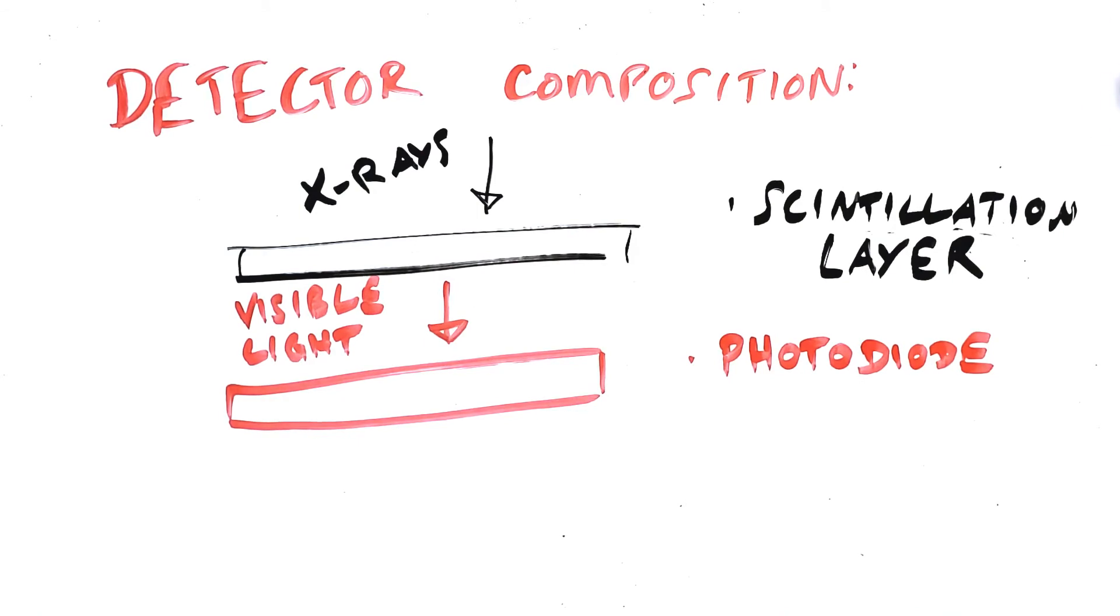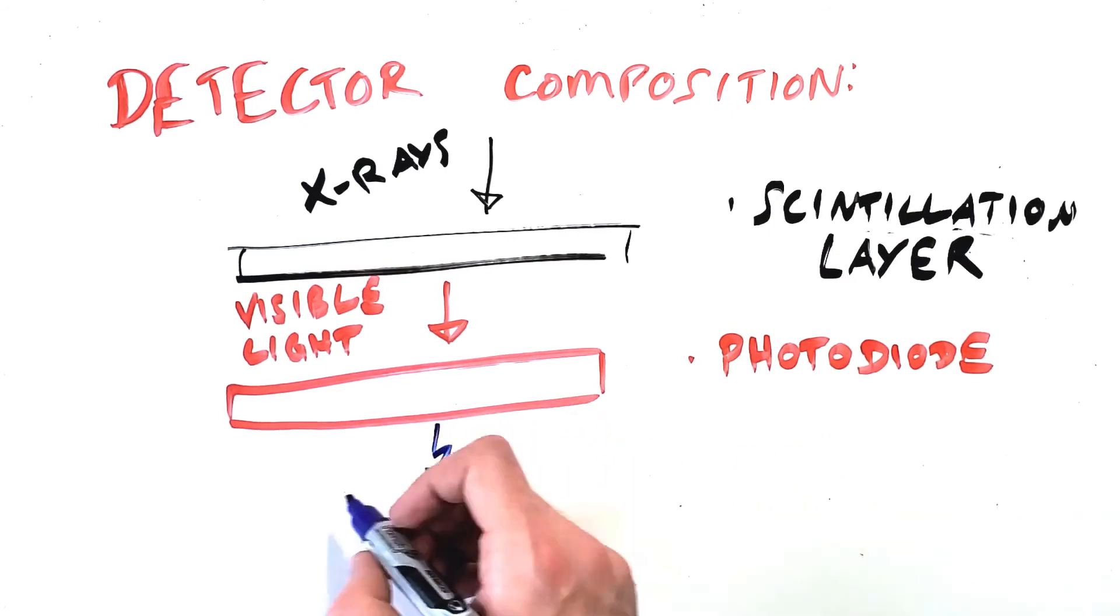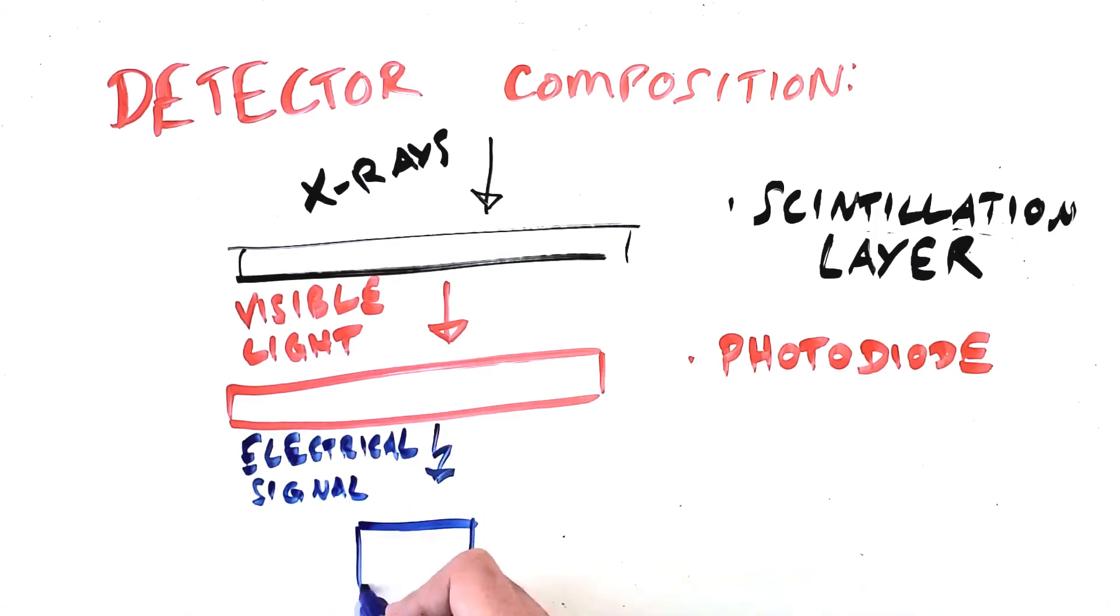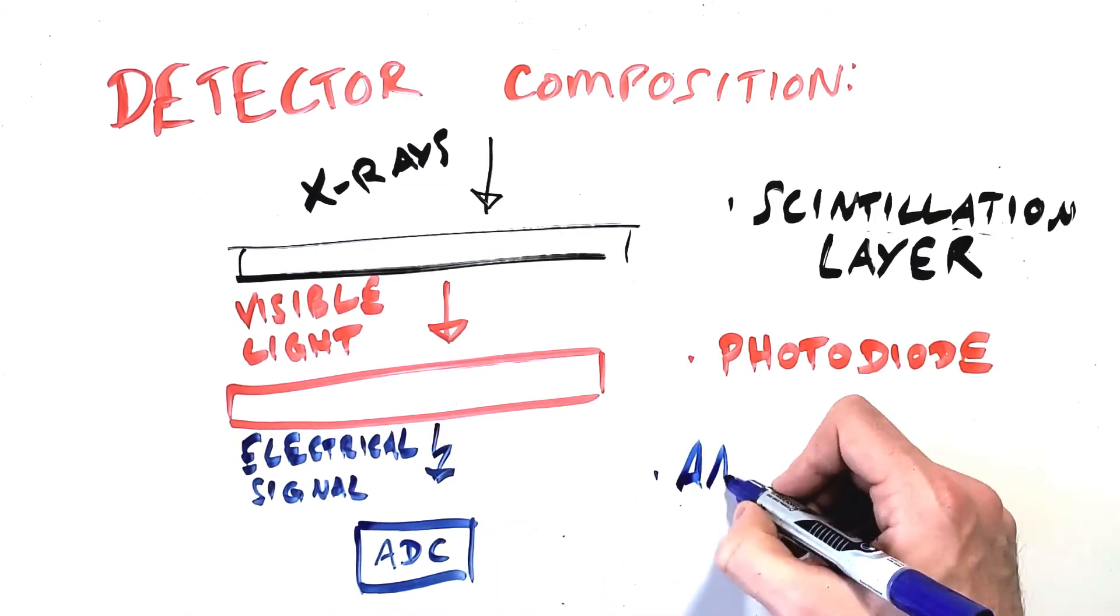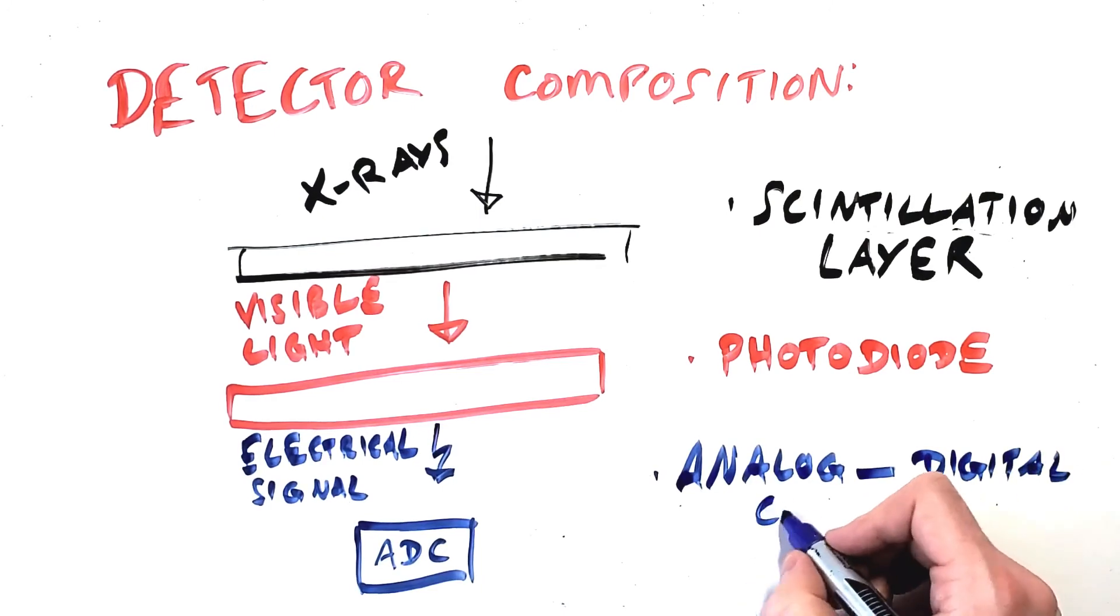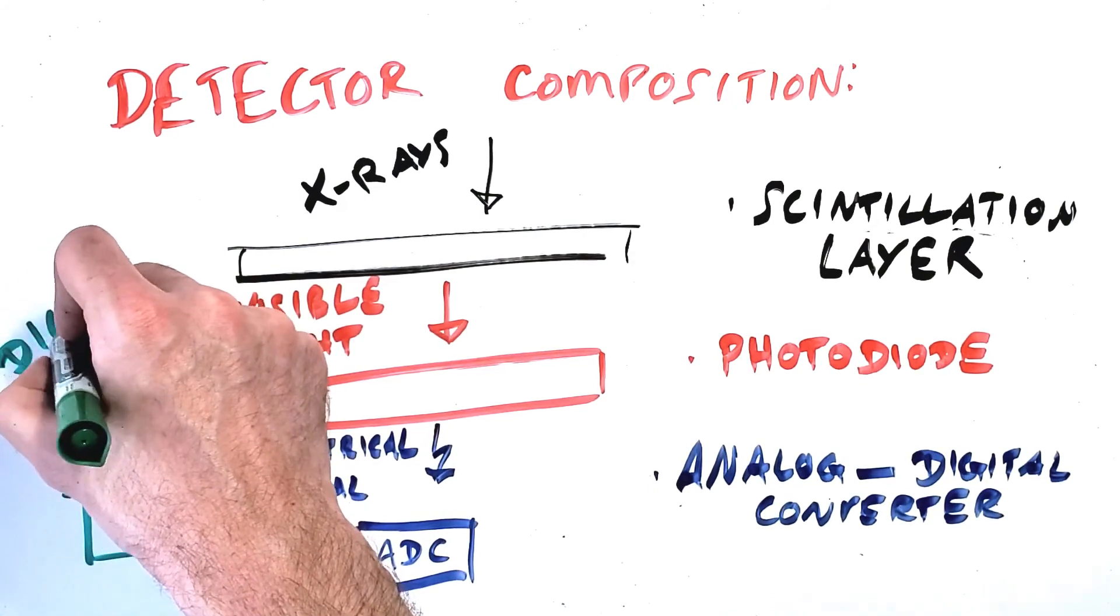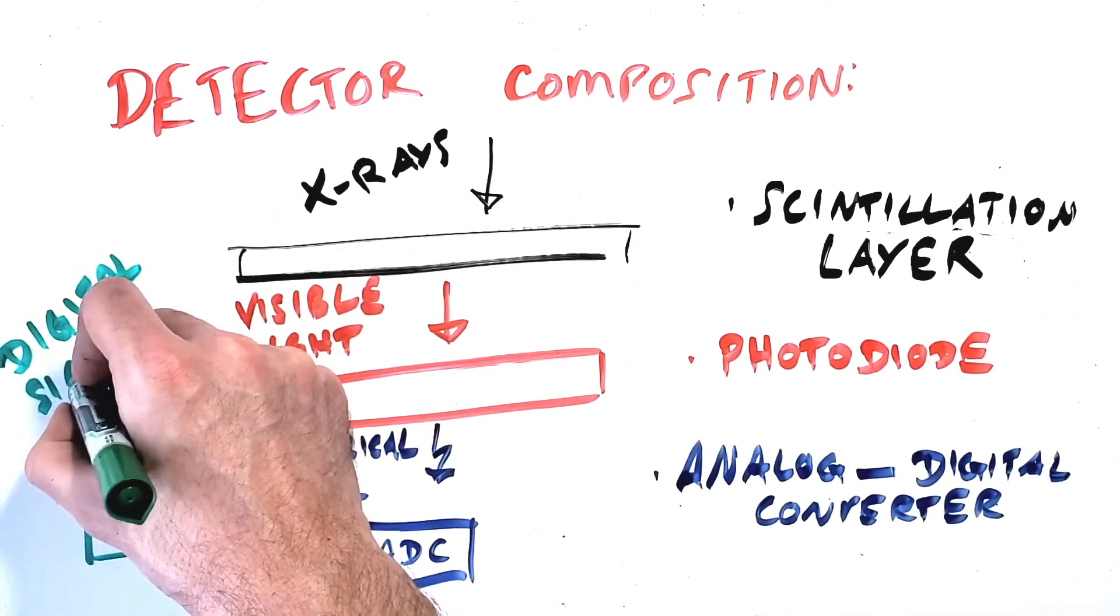The detector is an indirect type digital detector, meaning that x-rays incident on the detector are absorbed by a scintillation layer and converted into visible light. This visible light hits a photodiode which converts that light into an analog electrical signal. That analog signal is then converted into a digital signal by an analog to digital converter or ADC and at this point we have raw image data which is ready to be communicated to our workstation and processed into an image.